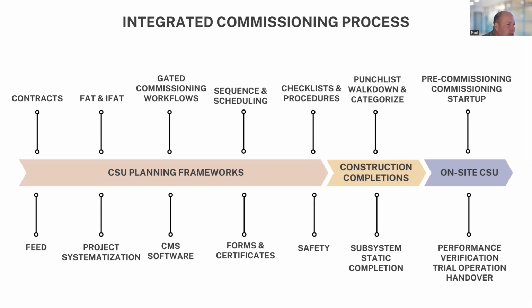Frank is asking, DCS and SIS should be integrated during FAT. Absolutely. Yep, anytime I've seen a project try to do their software integration later, during on-site testing for the first time, I've never seen that go well. We need to be integrating hardware and software in the factory to make sure these systems work. I've seen equipment damaged when they do that software integration on site, millions of dollars of damage. An oil pump was programmed incorrectly and it shut off while a high-speed piece of equipment was slowing down. The oil pump stopped, wiped the bearing, destroyed the unit. Millions of dollars in damage, months of delay, all because the software wasn't controlling that oil pump correctly. It never saves any time to try to do that integration on site for the first time. You always run into problems.